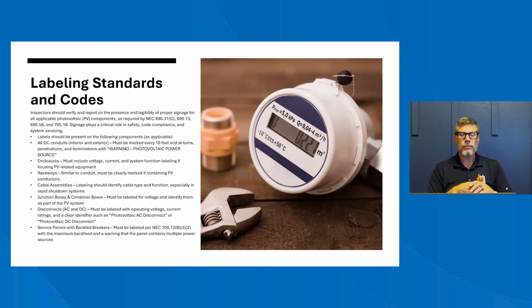Your DC disconnects and combiner boxes, those are going to have your maximum voltage, your maximum current, your short circuit current, system grounding method if it's applicable. Your AC output connection, that's typically in the service panel. That one is going to be specific.